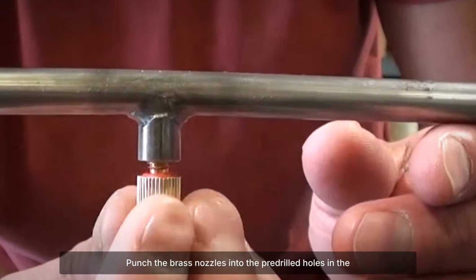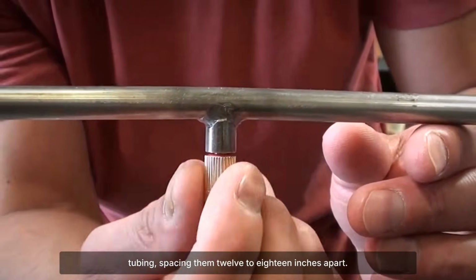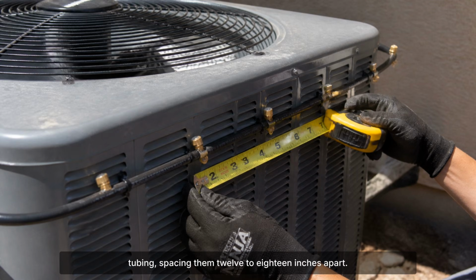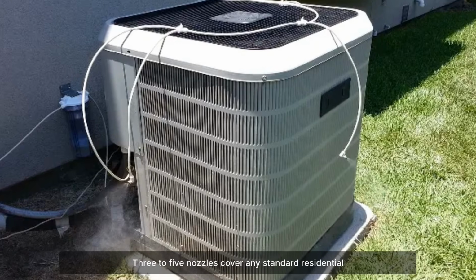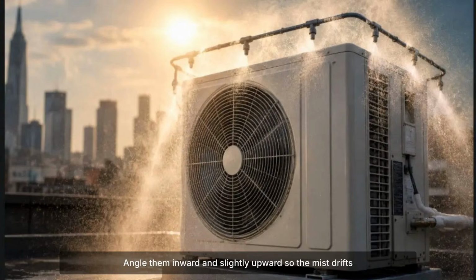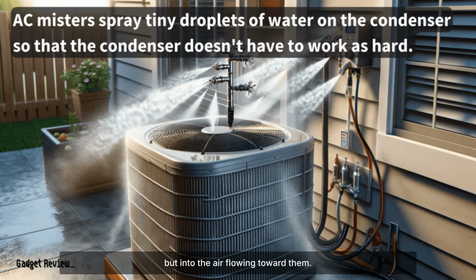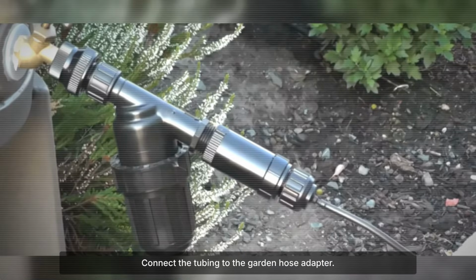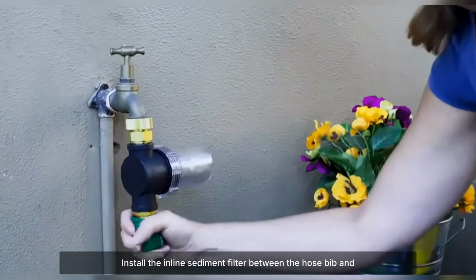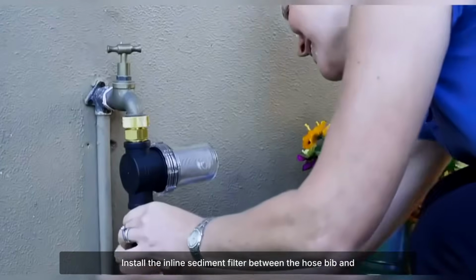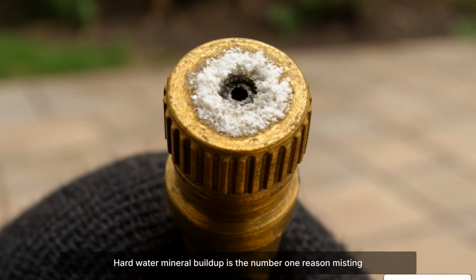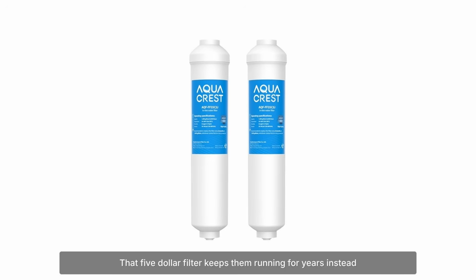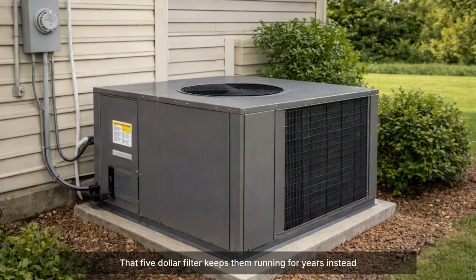Punch the brass nozzles into the pre-drilled holes in the tubing, spacing them 12 to 18 inches apart. 3 to 5 nozzles cover any standard residential condenser. Angle them inward and slightly upward so the mist drifts into the intake airstream, not directly onto the coil fins, but into the air flowing toward them. Connect the tubing to the garden hose adapter. Install the inline sediment filter between the hose bib and the adapter. Hard water mineral buildup is the #1 reason misting nozzles clog. That $5 filter keeps them running for years instead of weeks.